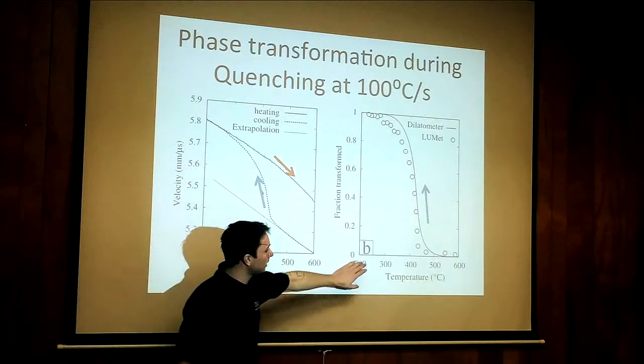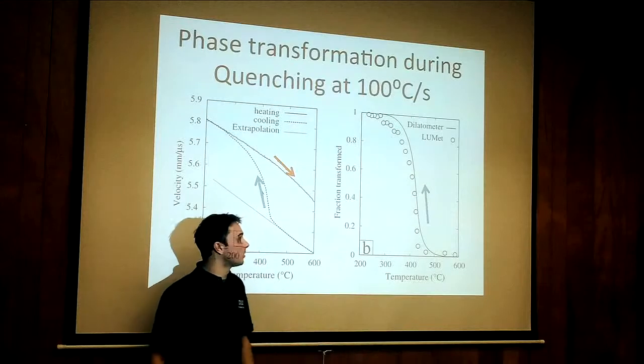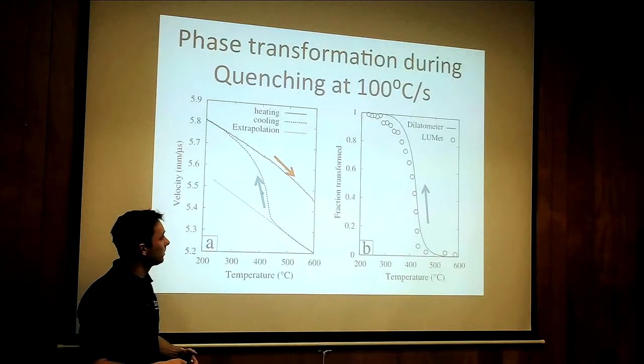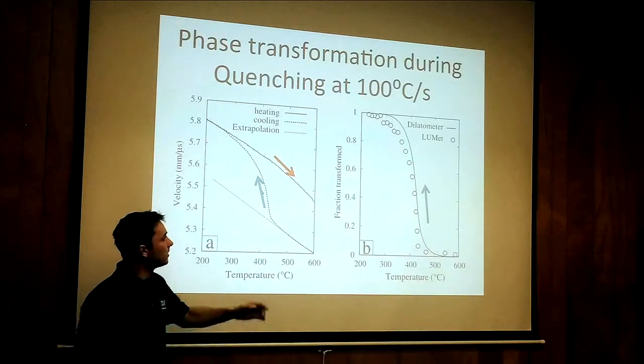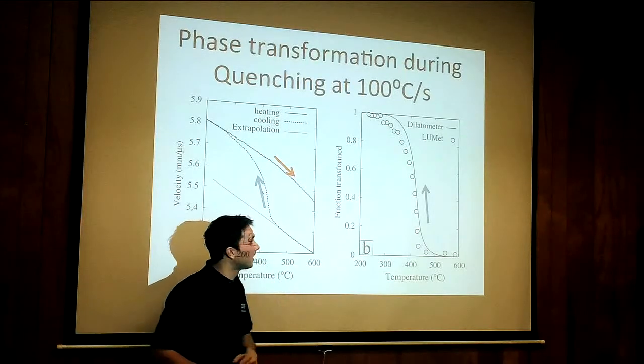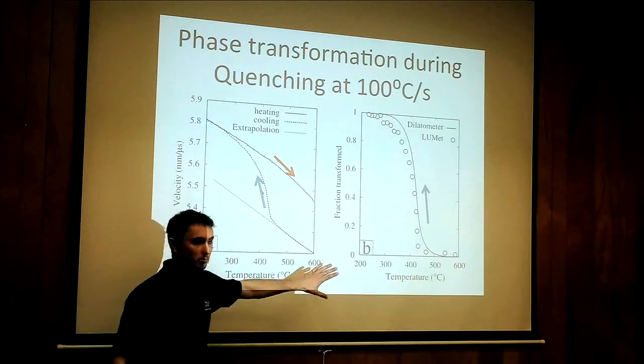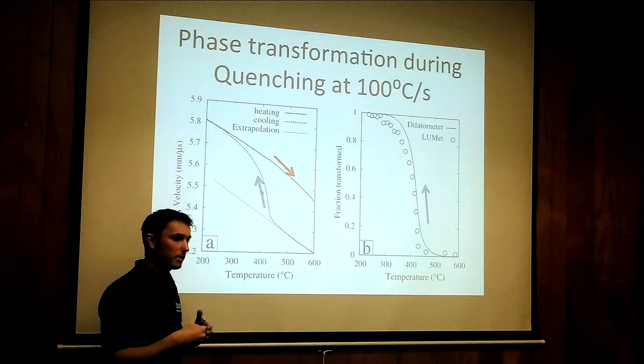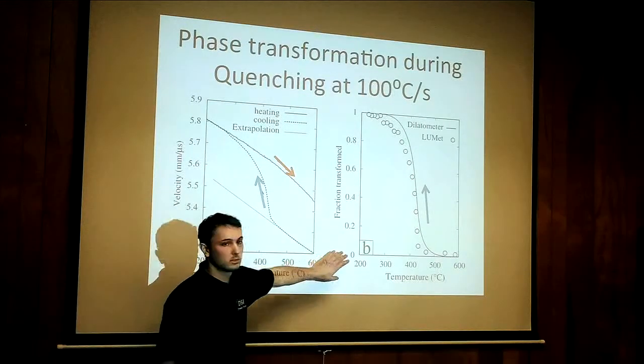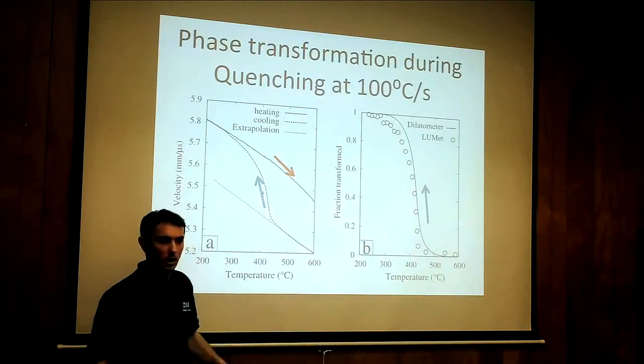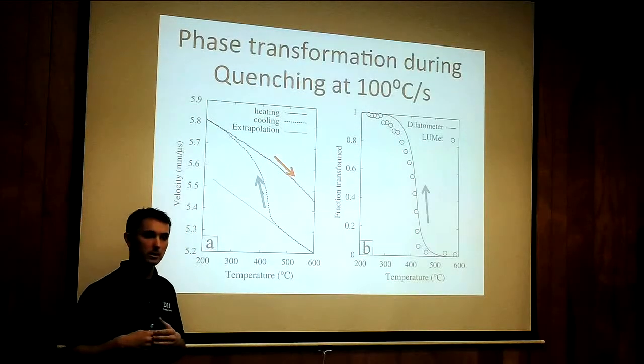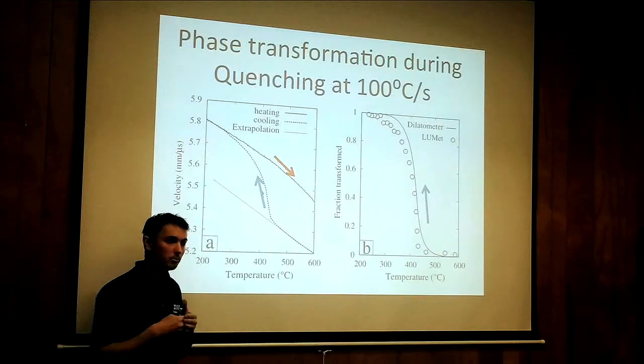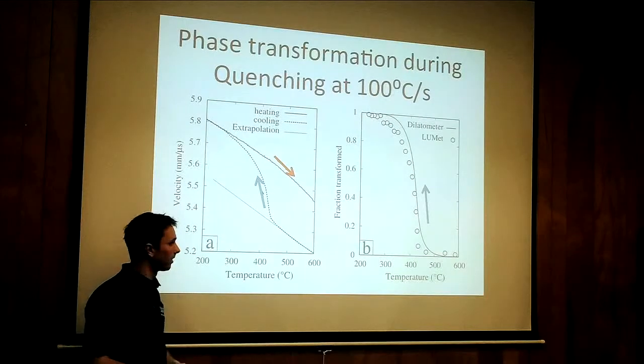And so what we see here is a direct comparison between a LUMET measurement of this phase transformation and a dilatometry measurement. I'd like to attract your attention that this type of measurement can be done during a very high cooling rate. Here this measurement is done at 100 degrees per second, and this is possible thanks to the fact that LUMET can generate up to 50 pulses per second.